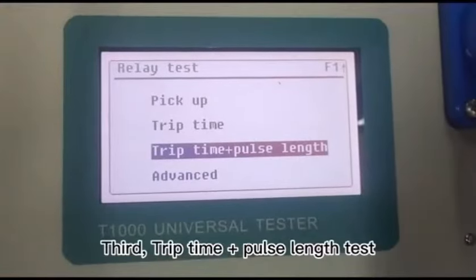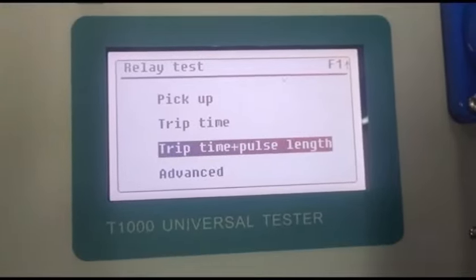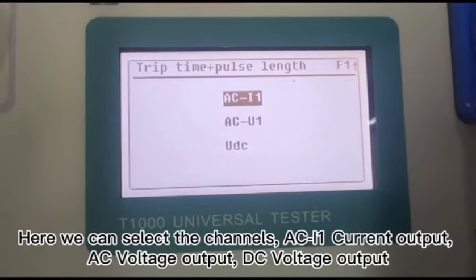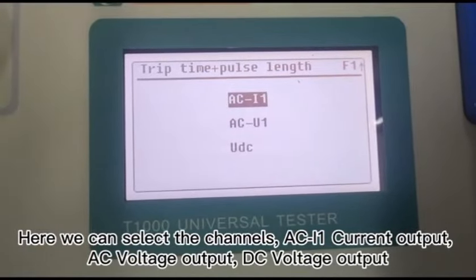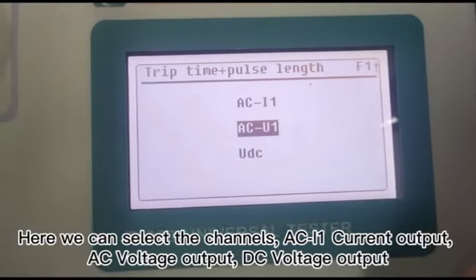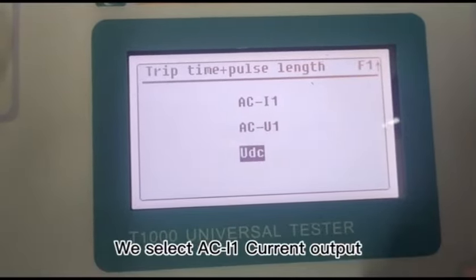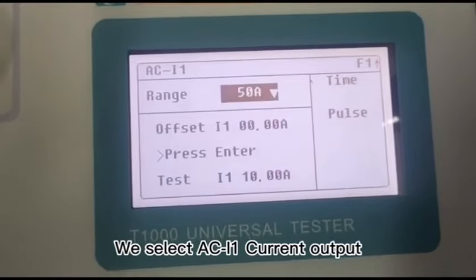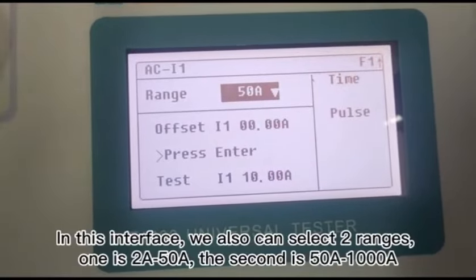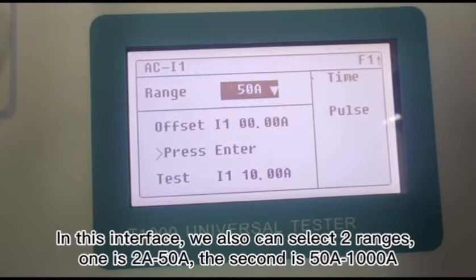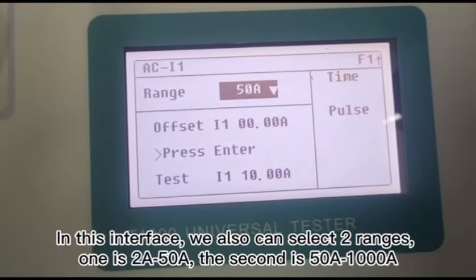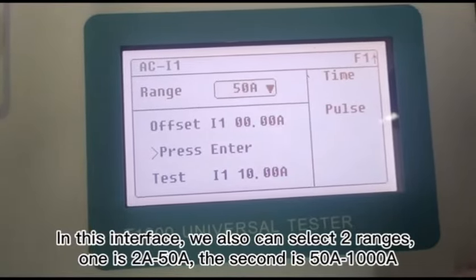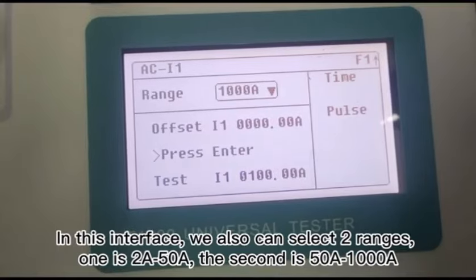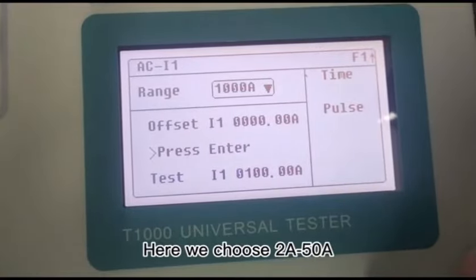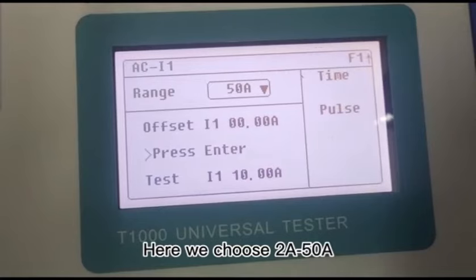Third, trip time plus pulse length test. Here we can select the channels, ACI1 current output, AC voltage output, DC voltage output. We select ACI1 current output. In this interface, we also can select two ranges, one is from 2 amperes to 50 amperes, the second is from 50 amperes to 1000 amperes. Here we choose 2 amperes to 50 amperes.